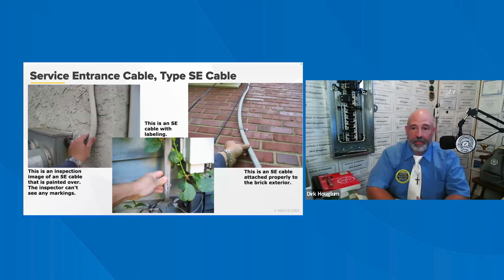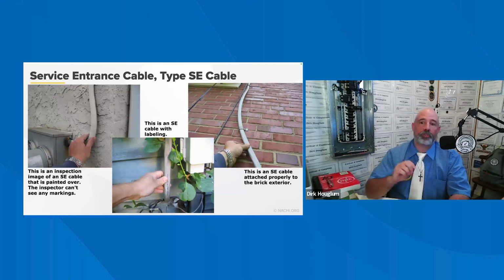Okay. The SE in SE cable stands for service entrance. You should know that by now. The cable is made to handle sunlight and physical wear. It's usually mounted directly to the building instead of being run through conduit. If the cable is in a spot where it can get hit or damaged, like near a driveway or where a car door opens, it needs to be protected inside conduit.